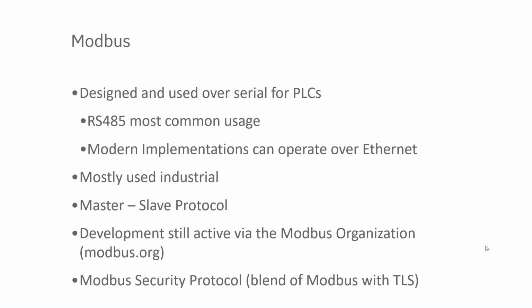Similarly, Modbus protocol was designed for serial networks. Most common use is RS-485. It's mostly used in industrial applications. It is similar to DNP. It is a master-slave protocol. It does support Ethernet with the modern implementations, and it does also support secure authentication, but in a different way.